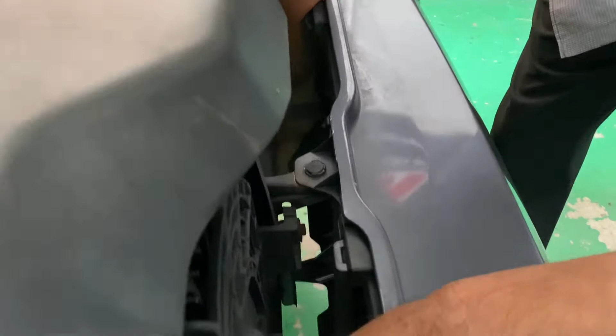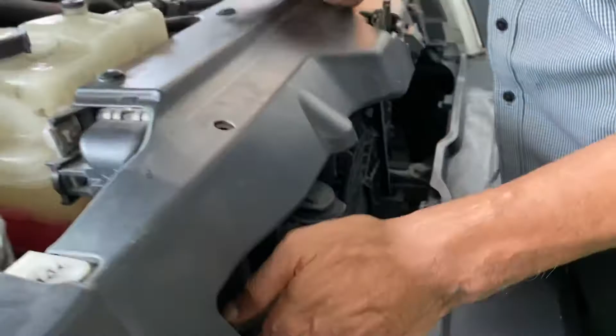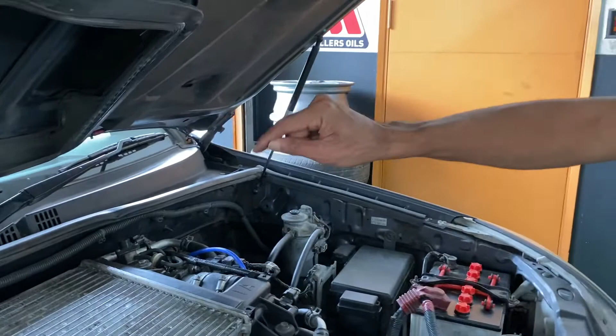Out of the condenser, down here, it will go to a service valve line. Then this is the liquid line, and this liquid line will go back to the expansion valve, then goes to the cooling coil. That is the basic line. You must observe the line first.